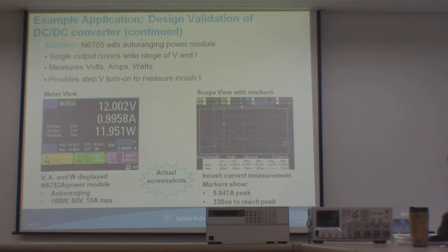So typically on a power supply, this is a voltage-current power supply. Typically, you have this type of characteristic, right? So this is your V max, voltage max, and this is your current max. So this is typically a one-quadrant DC power supply.